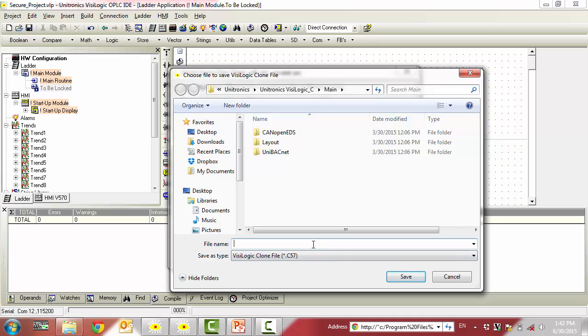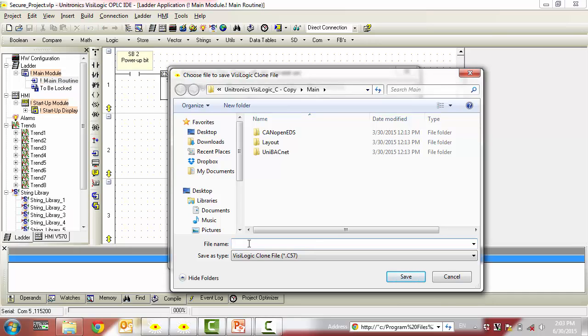Now, you will select a location to save this clone file to. Note that the clone file name must be exactly 8 characters long. And also note that the file extension, in my case .c57, corresponds to the controller that you have selected in the hardware configuration.